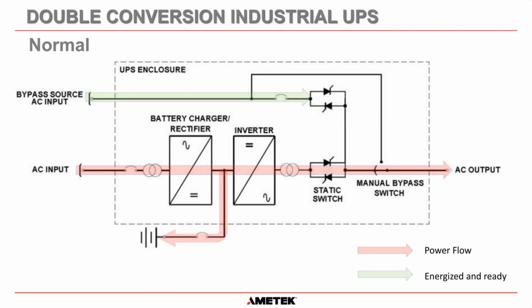And then we also have our bypass source AC input, or our reserve supply. We can see that this is energized and it's ready to go at this static switch here, but this static switch is off. It doesn't need to be on just now. So it is there waiting to go. The inverter has synchronized itself to the bypass supply, and we'll get to that later on. And if necessary, we can transfer to bypass if there was a reason to do so. But at this moment in time in normal operation, the bypass just sits there, is ready to go, but it is not supplying any power.